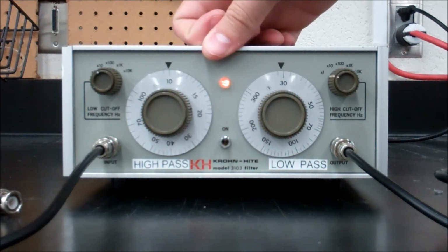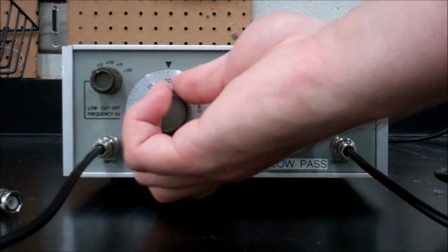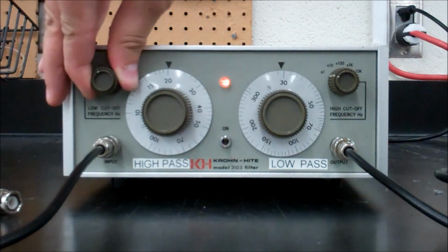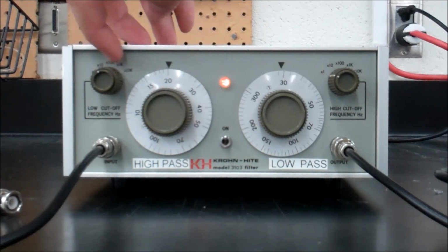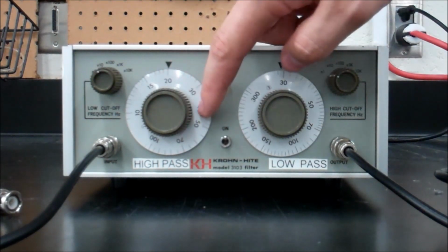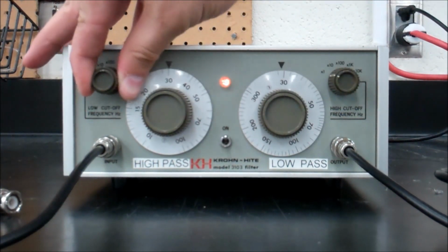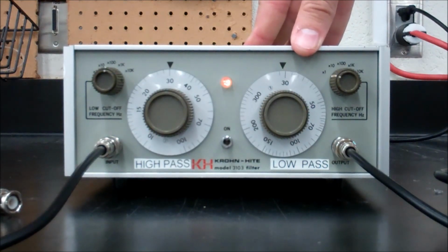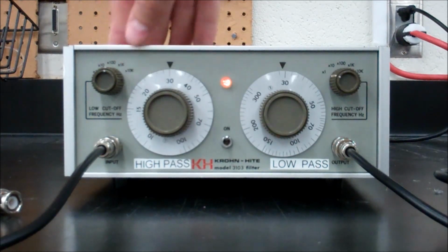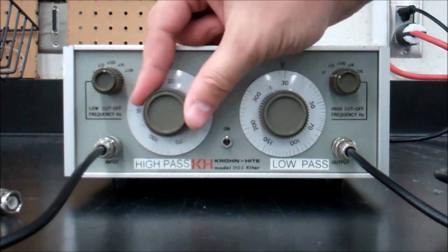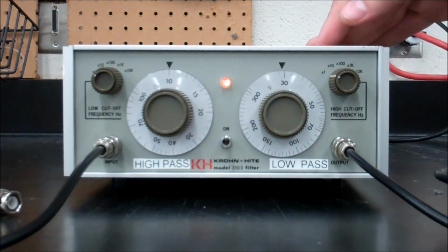So let's say we want to set a cutoff frequency at 200 for the high pass. Then we turn the big knob to 20, and then we turn our little knob to 10, because 20 times 10 is 200. So this little knob up here is a multiplier for the value you set here. So say I want to set 3000. I could go to 30 and set my multiplier to 100, which is 3000. So that way I can set my high pass to certain frequencies based on this knob and the multiplier. If I only want to set it at 10 hertz, then I turn my knob to 10 here and turn my multiplier to 1, and I have 10 hertz.